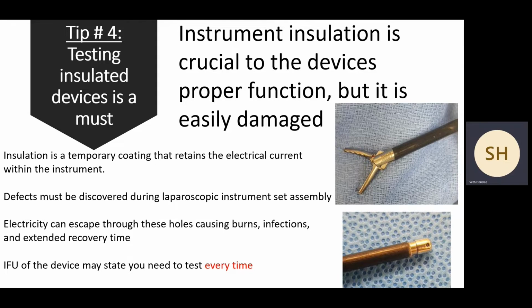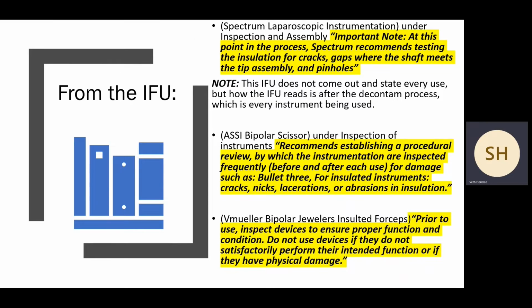Now, as I said, we're going to back some of this up. If AAMI isn't where you want to rest your process on, well, we can look at Spectrum for their laparoscopic instruments. At this point in the process, Spectrum recommends testing the insulation for cracks, gaps where the shaft meets the tip assembly, and pinholes.